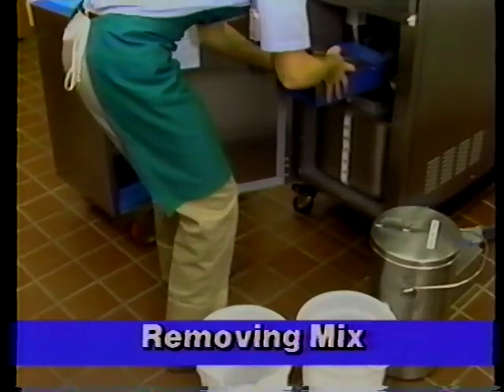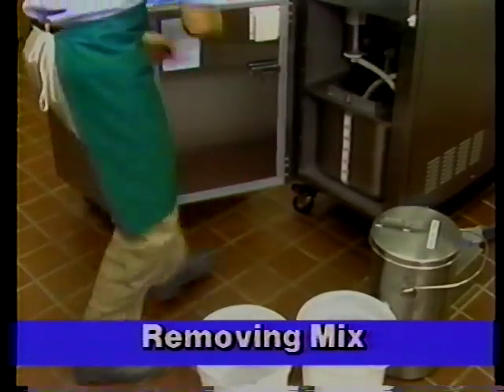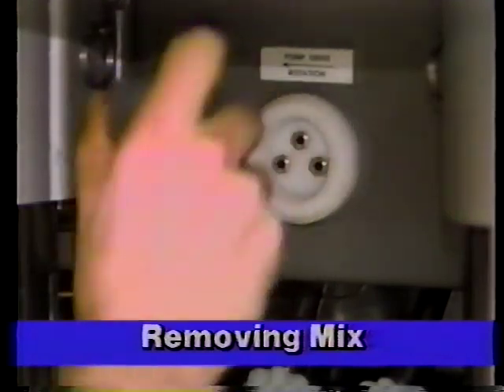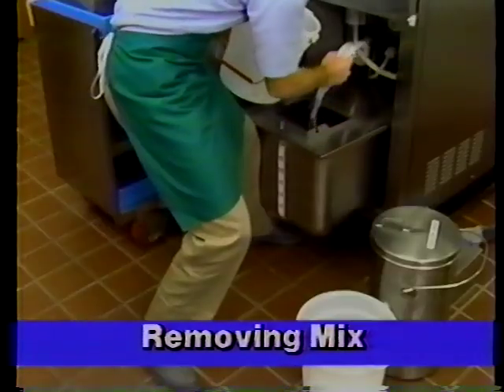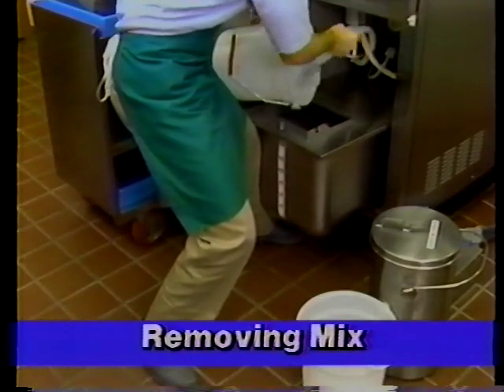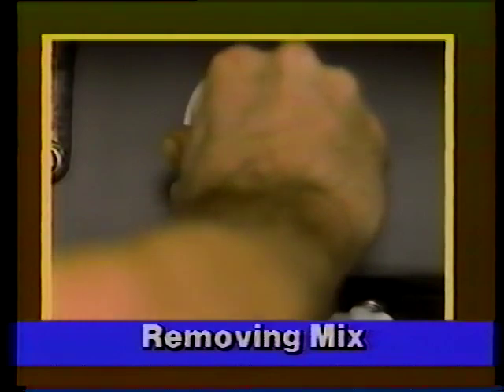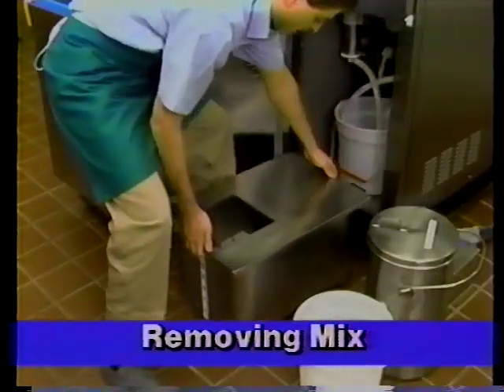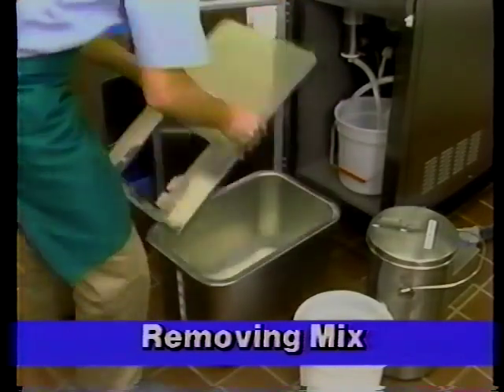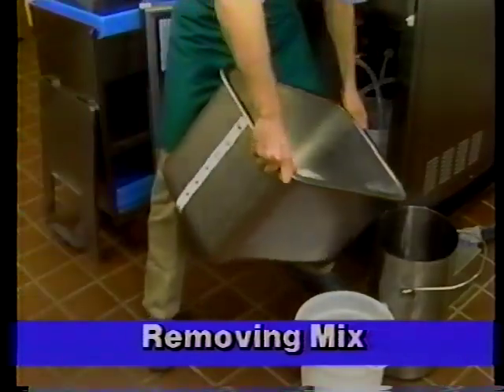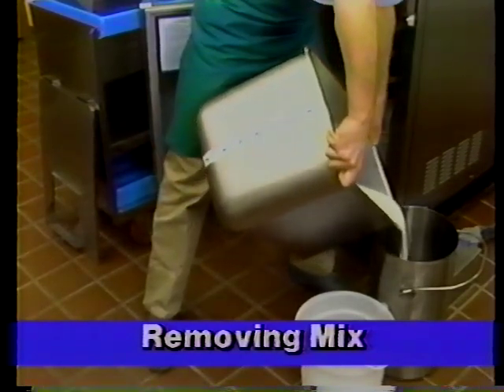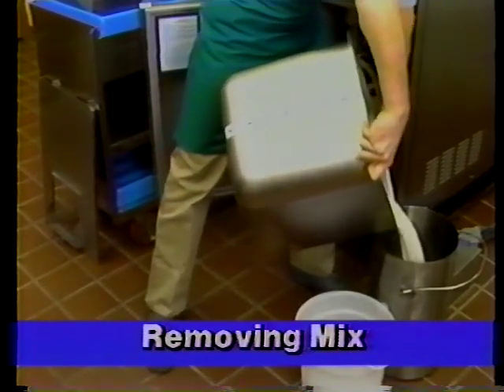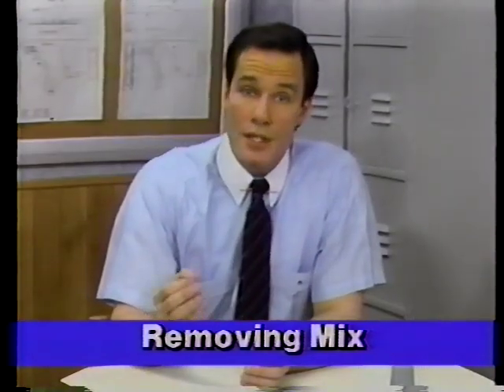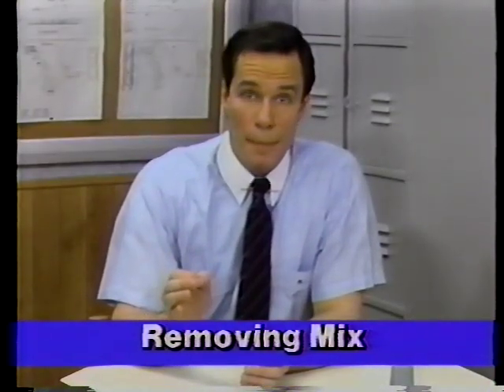Open the mix cabinet door, remove the funnel, disconnect the mix probe, then place the ends of the suction lines in the empty sanitized pail to catch any drips. If your store has a mix probe that looks like this, remove it this way. Now take the mix reservoir out and remove the cover. Then pour the mix into the sanitized rerun container. Be sure not to get your hands in the mix when you do this. Then cover the container with a lid that says Shake Mix Rerun.